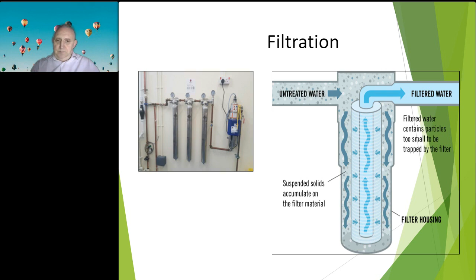So if you look at a purification system, it's a combined system, okay? If you look bottom left, feed water in, pre-filter. Then we have a pump, RO plant, okay? Water quality sensor, sanitization ports all the way along, okay? Then we have a reservoir. We have a ring main, a loop.